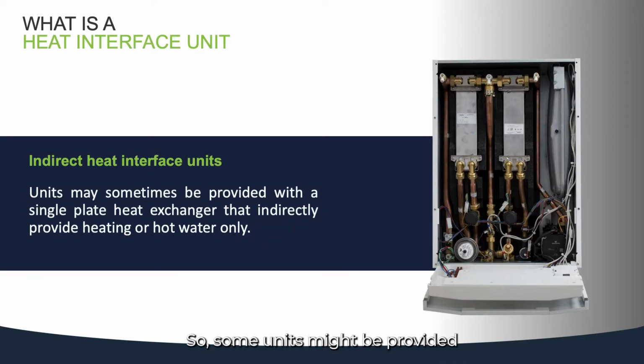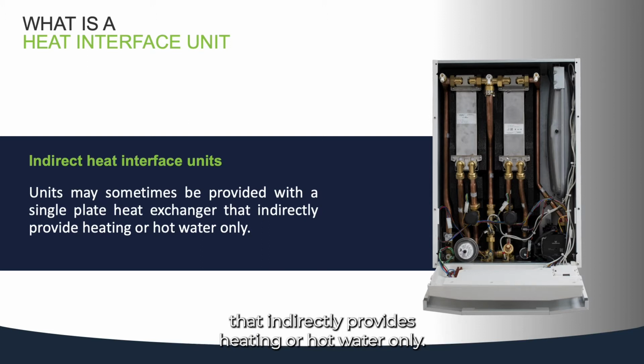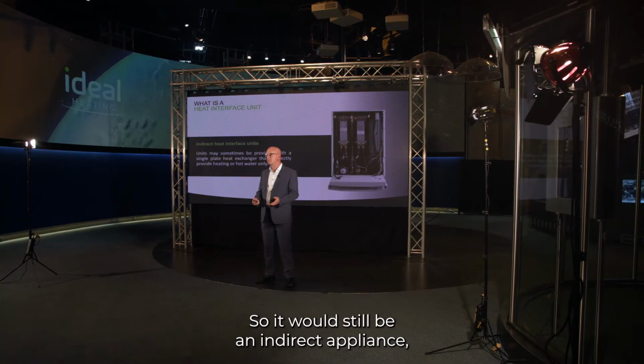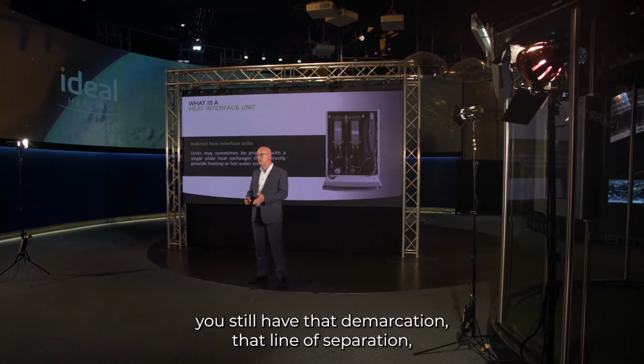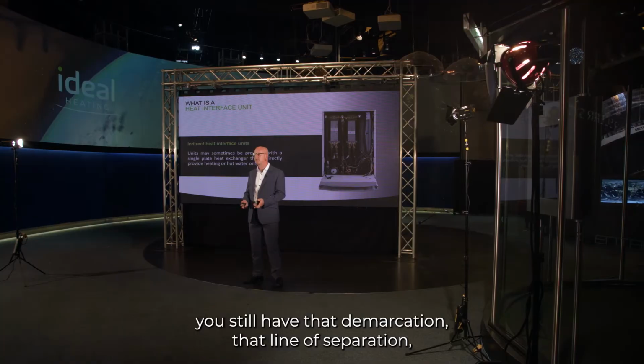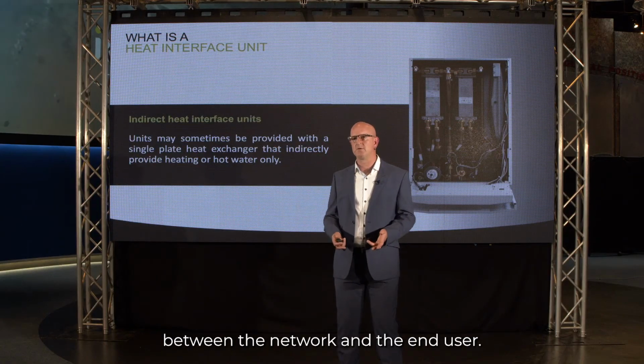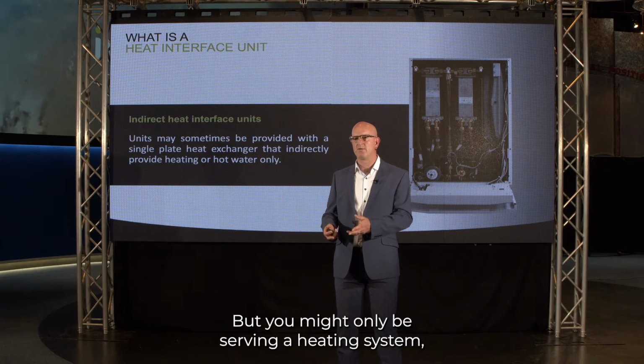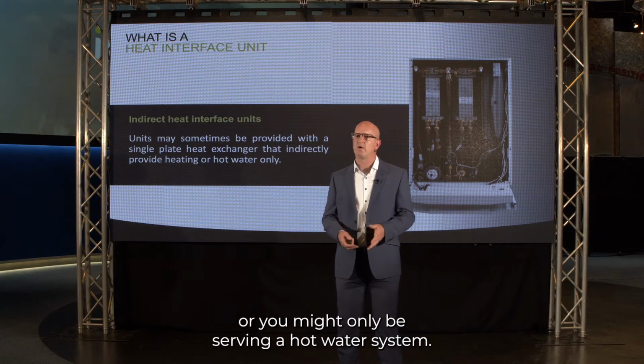So some units might be provided with a single plate heat exchanger that indirectly provides heating or hot water only. So it would still be an indirect appliance. You still have that demarcation, that line of separation between the network and the end user. But you might only be serving a heating system, or you might only be serving a hot water system.